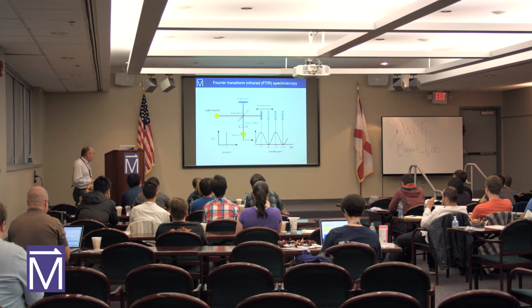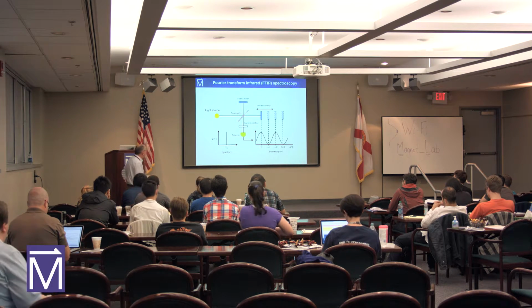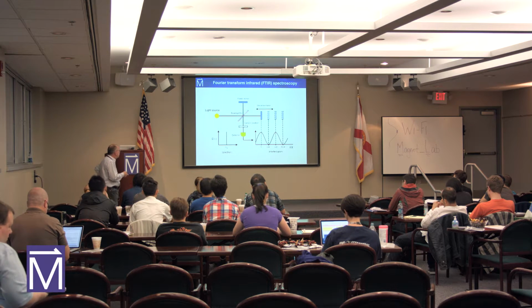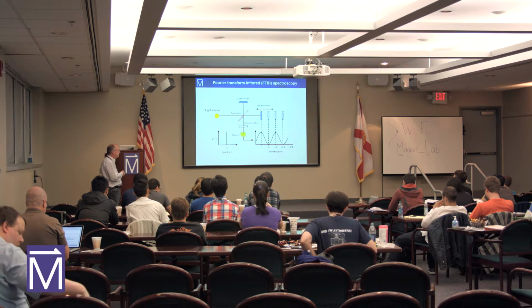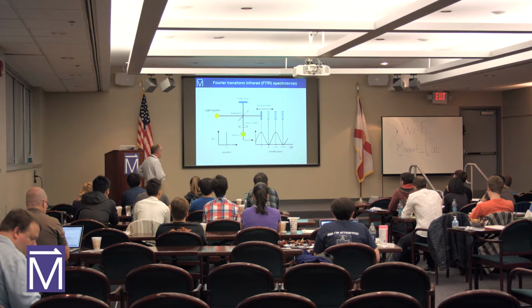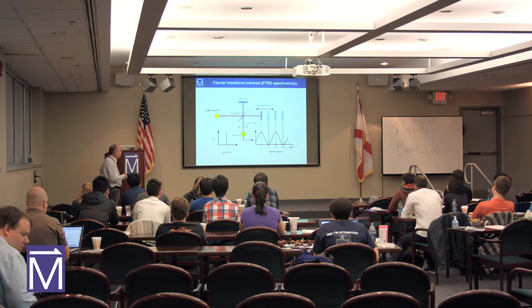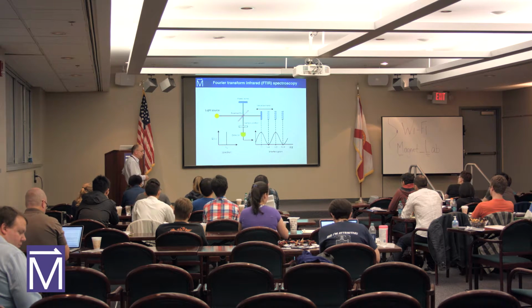I think the most widely used and best technique for IR spectroscopy is Fourier transform spectroscopy. It's based on the Michelson interferometer, which is depicted here. Let's send monochromatic light first from the light source. There is a beam splitter, a fixed mirror, and a movable mirror. Then our interferogram, or Fourier image of this line, will be just a sine function. So if we measure accurately the position of the mirror, actually the signal to the detector as a function of the mirror position, we can recover the interferogram, then perform an inverse Fourier transform and recover the spectrum.